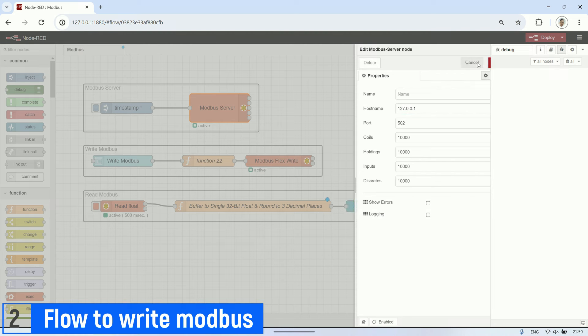To write to a Modbus register, I use a form node to input the value that will be written to the Modbus register. Make sure the type is set to number. Next, I use a function node to write the input value from the form to the Modbus register. Since the value is a 32-bit float, it requires two registers.